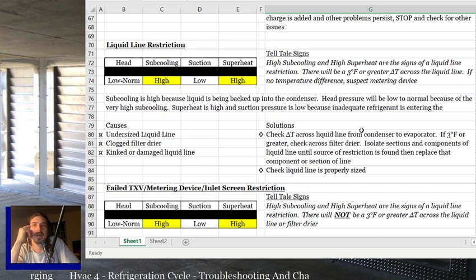So subcooling will be high, suction pressure will be low, and then superheat will be high. So the telltale signs of a liquid line restriction is high subcooling and high superheat. If you have a high subcooling and high superheat at the same time, it's either an issue in the liquid line or an issue at the metering device.